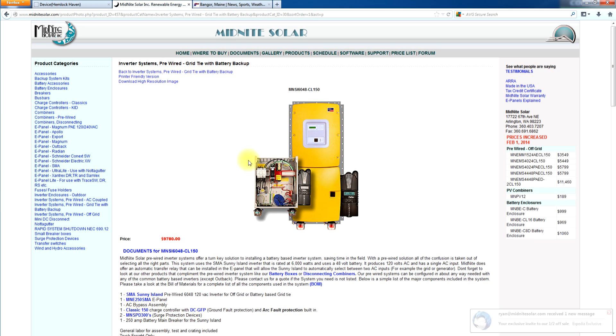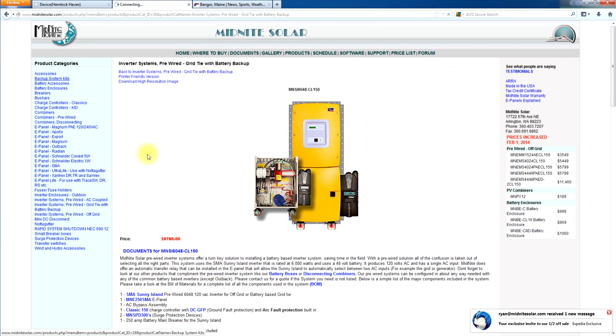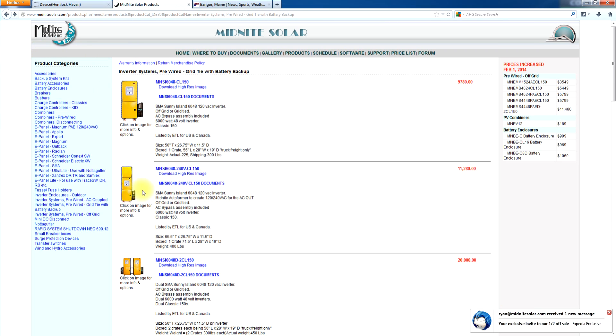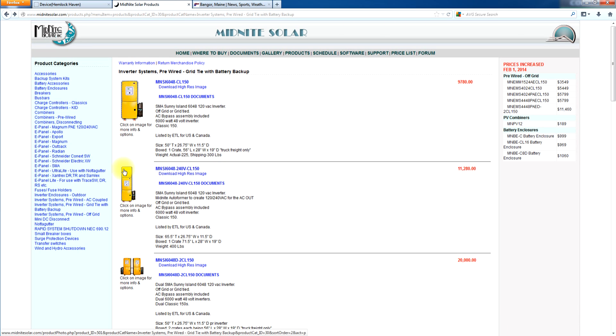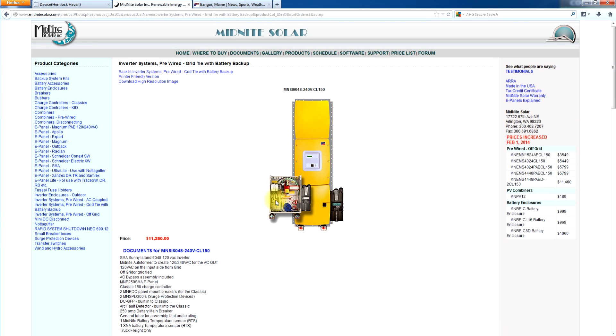So as you see there, there's a 120 volt version of the grid tied battery backup Sunny Island and you can look down through and we make a 240 volt with the auto transformer on it. Same exact thing except this gives you 240 volts for your critical loads if you had a well pump or something you need 240 volts. This has the auto former, still grid tied, still communicates with the classics.